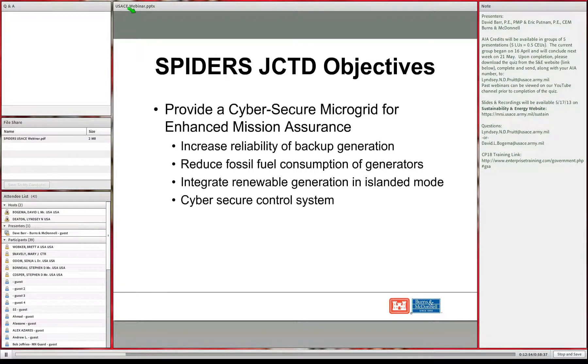Generators can also be tested without taking an outage to their served loads, which is currently unavoidable. Another benefit of SPIDERS is increased situational awareness across the installation. At Pearl Harbor, utilities operators for NAVFAC had SCADA visibility only on the Pearl Harbor side; the Hickam side had no SCADA at all. By adding microgrid controllers to feeders on the Hickam side and connecting back to the Pearl Harbor utility command center, operators gained visibility into loads on the Hickam side.